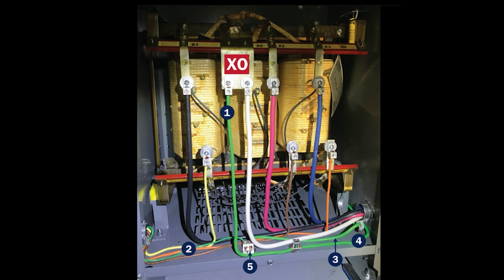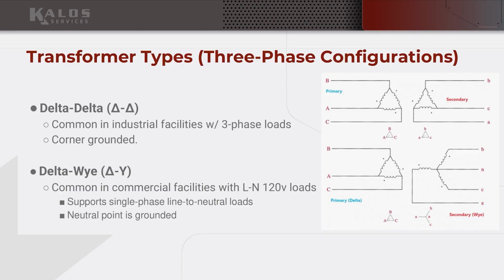They're wired together in two configurations: a delta-delta configuration and a delta-wye configuration. Delta-delta is where the three single-phase transformers are wired in a triangular fashion - call this coil A, coil B, and coil C. C and A make a connection, A and B make a connection, and B and C make a connection, in a triangular pattern. So you have one configuration that's delta primary and delta secondary.